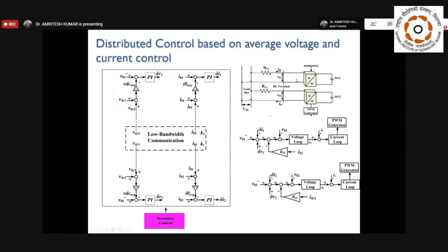Okay, and based on that, it is going to give commands to the individual converters. For individual converters the control is different. It's not going to be the same as in the centralized controller. The central controller gathers all the information from all the converters, and this secondary controller is going to give commands to each individual primary controller on what to do. So even if the control for one converter is missing, others can work fine. That's why the chance of failure is lower in this distributed secondary control.